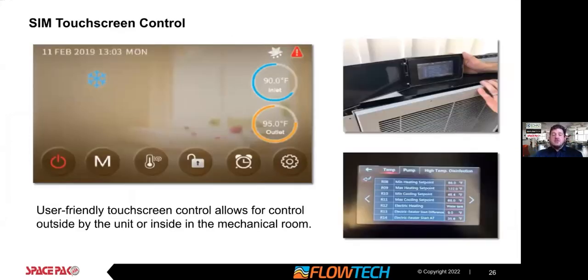The touchscreen control is a feature of the SpacePak monoblocks that are out, and also the split unit, which is a differentiated feature. It's not on the other types of equipment out there, and it's just a really handy and effective tool. This is a way for technicians to program the unit on startup, adjust water temperatures, set the mode, and it gives you some really great diagnostics. You can see on the right and the left, those circles are your supply and return temperatures, so a technician can see exactly what's happening with the temperatures of the unit.